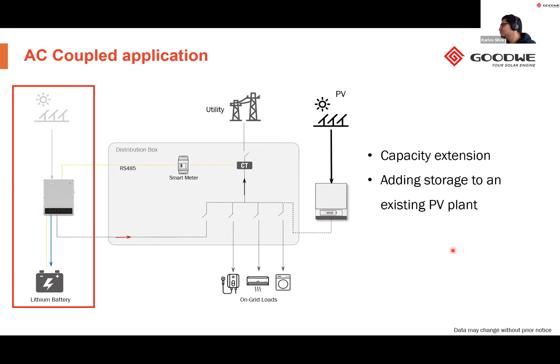So what I'd like to introduce to you is our ET series inverter for the DC coupled solutions or applications. It is a three-phase high voltage inverter. High voltage means that this inverter will be able to be connected with high voltage batteries, generally from 180 volts and above. This inverter is available in 4 power classes: 5, 6.5, 8 to 10 kilowatts. It has 2 maximum power point trackers. It has a maximum discharge and charge power capability of 5 to 10 kilowatts. However, that does depend on the inverter size, and it also depends on the battery system voltage and capacity.